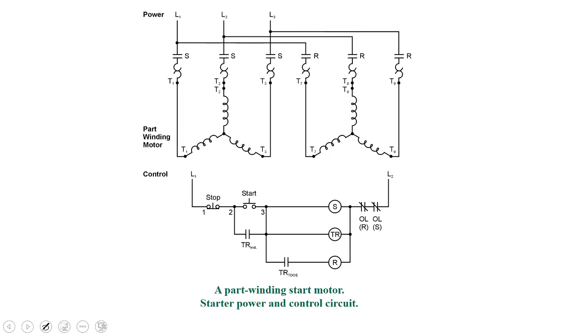Okay, we're getting into some of our different starters. The first one we're going to look at is called a part winding starter. This isn't a true reduced voltage starter, but the motor has two sets of windings, which are parallel with each other, and they're parallel Y. We would energize the first set of windings, and then within 2 seconds we'll energize the second set of windings to get it going. So this is the start-only winding, and then they'll both be energized for the run.